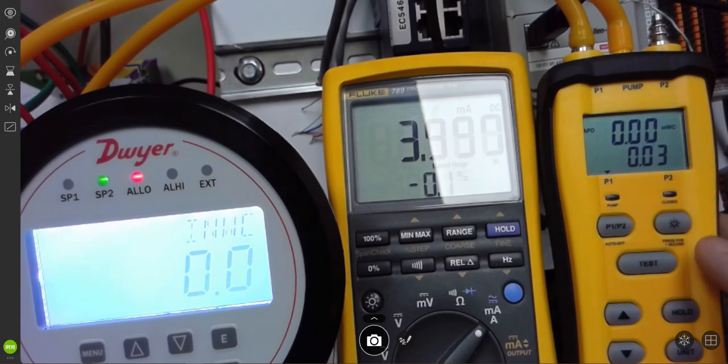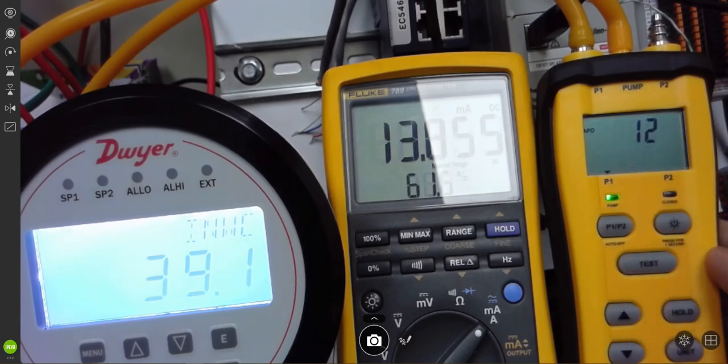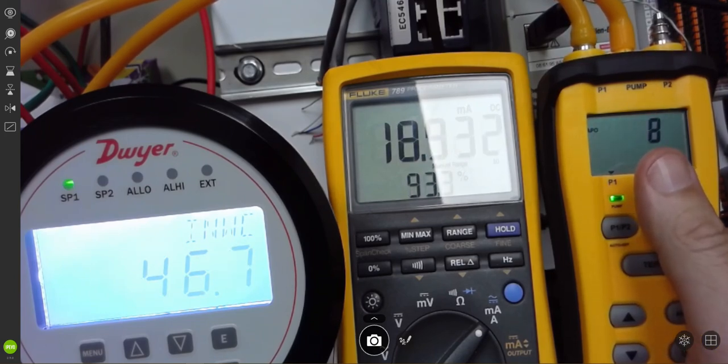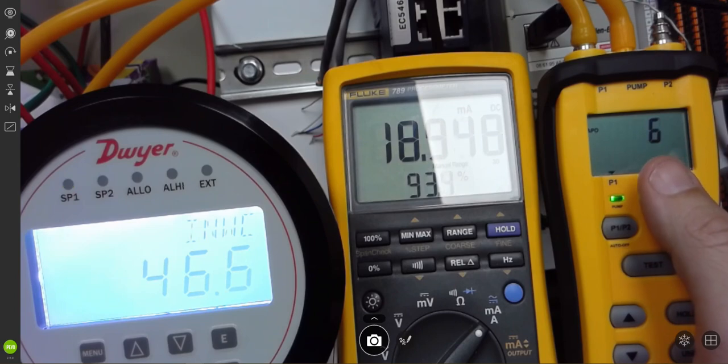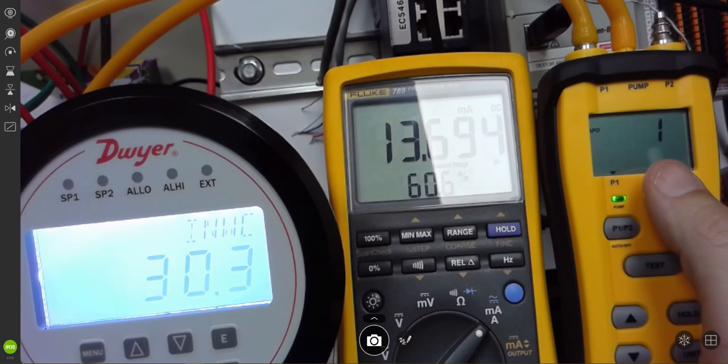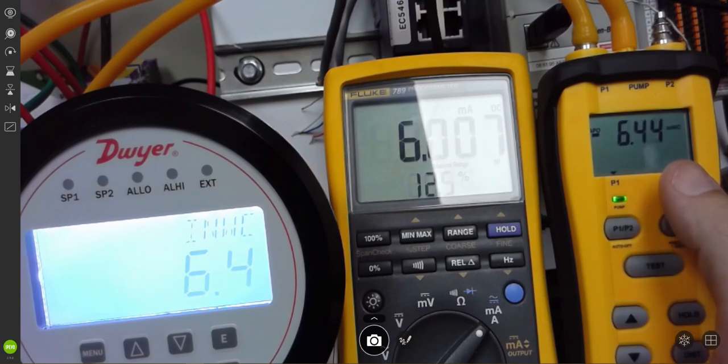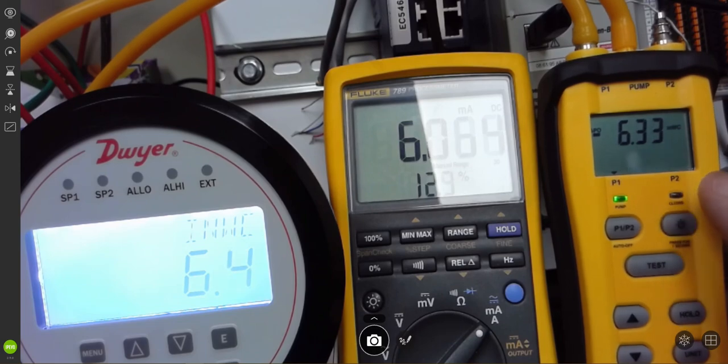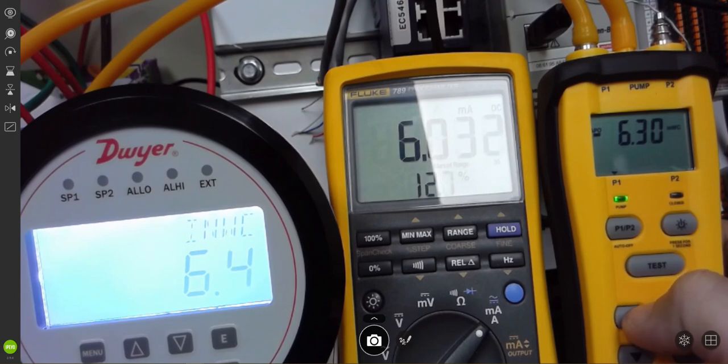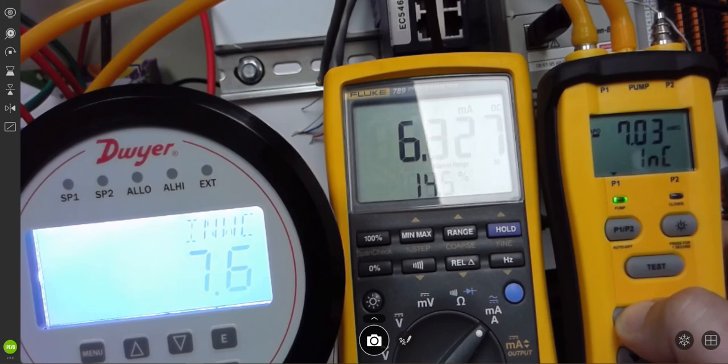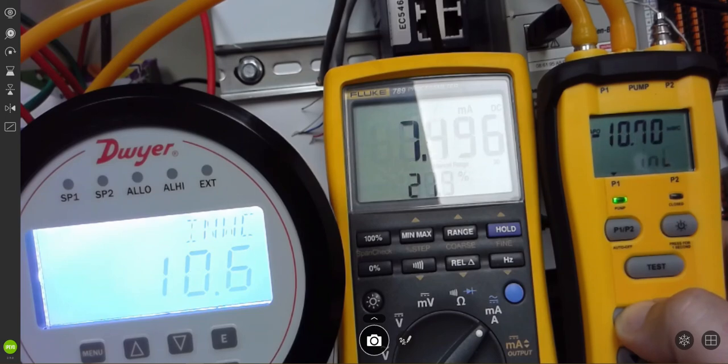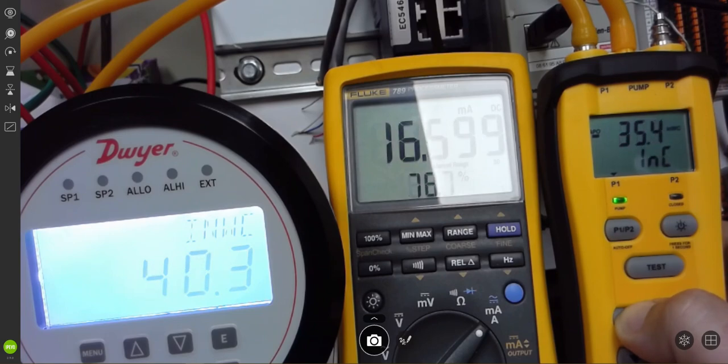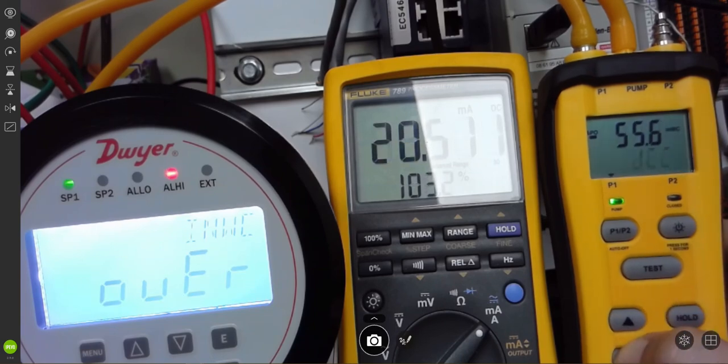Here we're going to run this up. So we're going to hit the test button. Here you'll see it's settling in. Technically, you're not even supposed to bother looking at that until it goes and displays inches of water column. Okay, so that's just kind of where it landed. You'll have to wait for it to stabilize because when you run this up, you can actually hear the little pump increase in speed. It's a little PWM vacuum pump, very small. So we're going to hold this and we can just hold it down and that puts us into high speed. And we're going to run this all the way up. And once I get close to 50 inches of water column, which is the max range of this meter, then I'll start sneaking up on it and we can verify that it is actually. You'll notice some alarm lights and stuff are coming on. Went too high. Bring it back down.